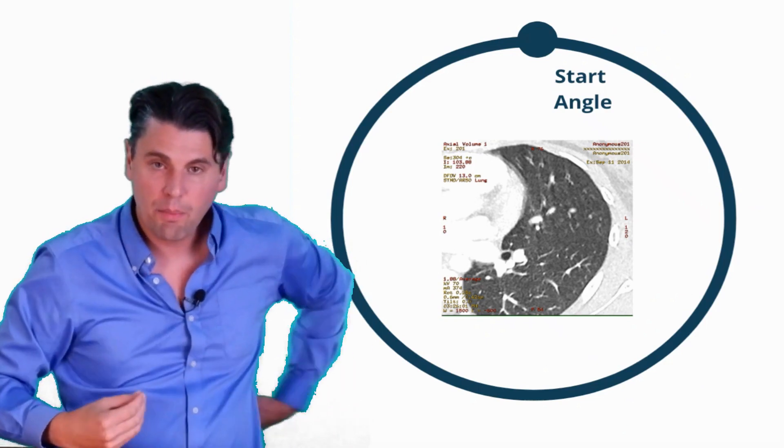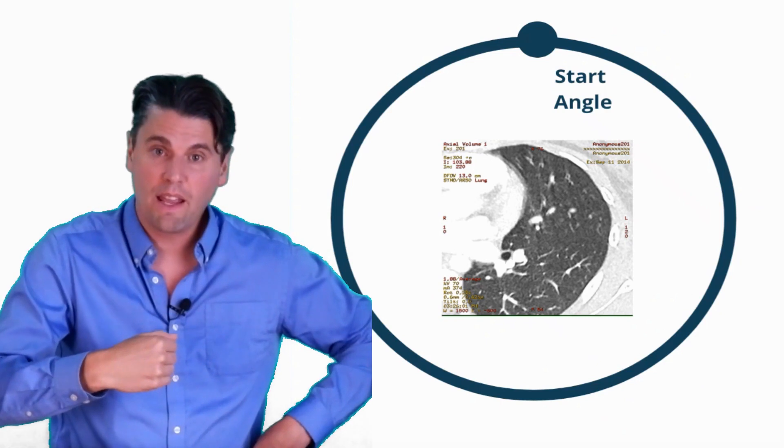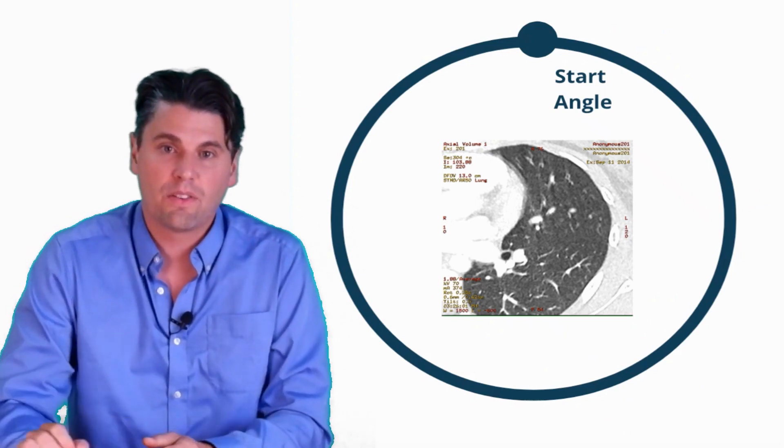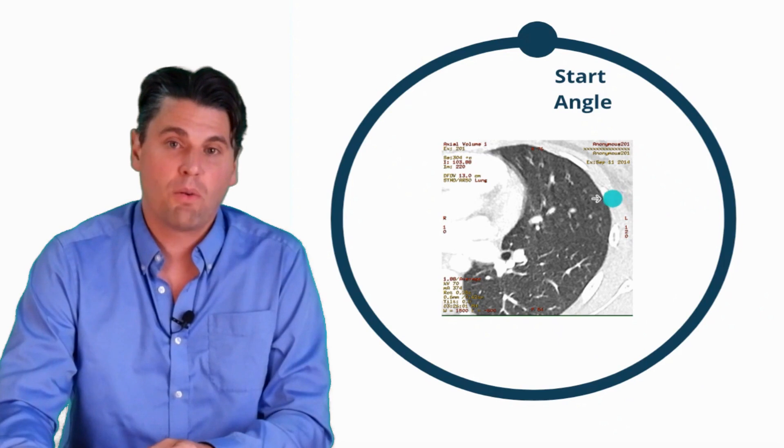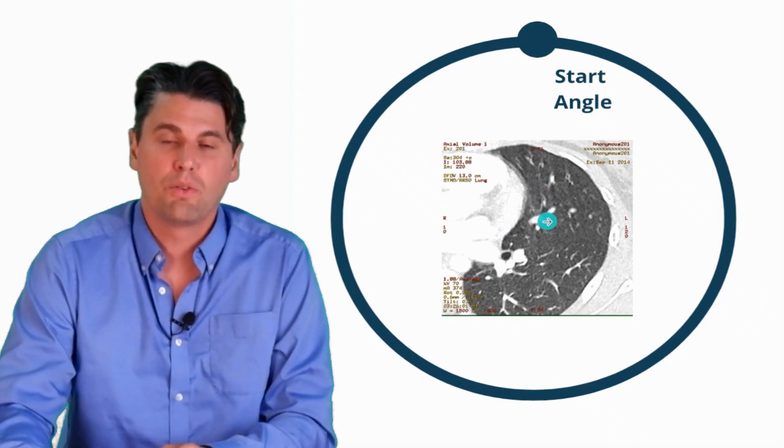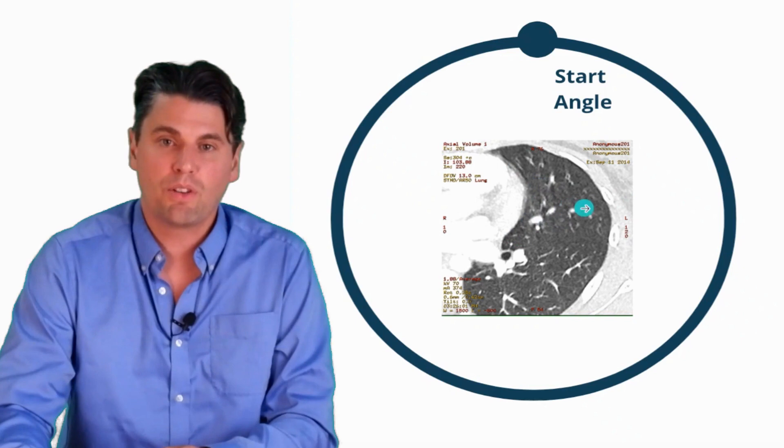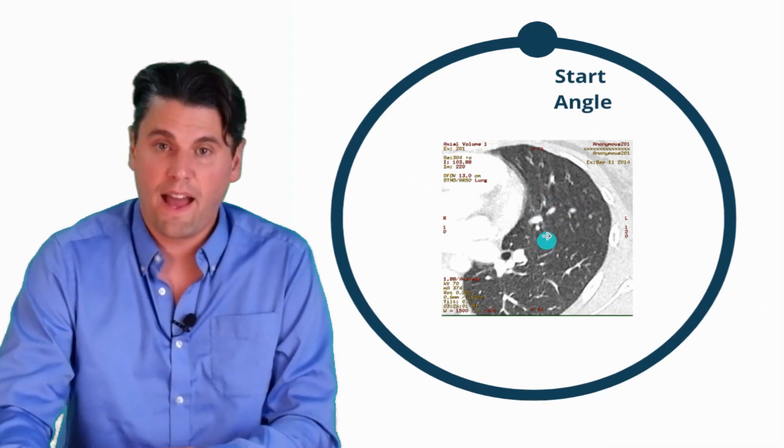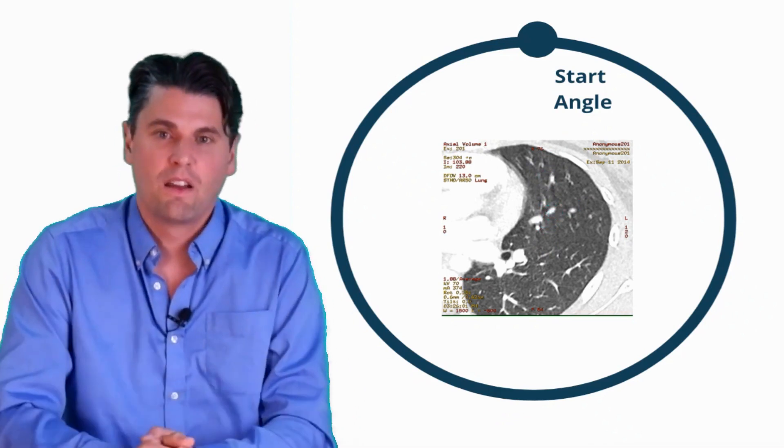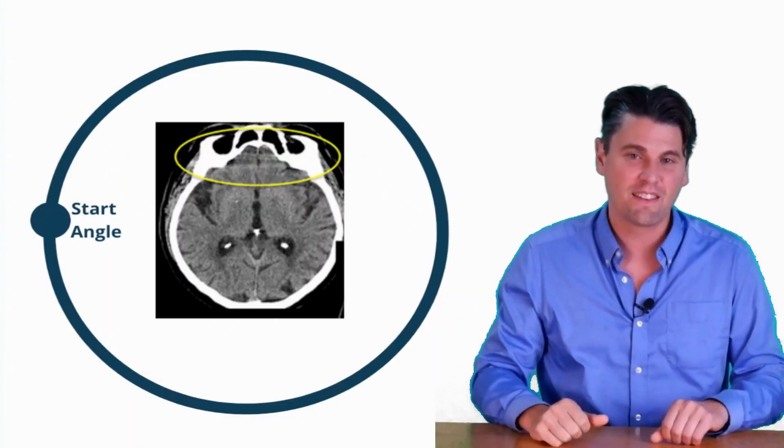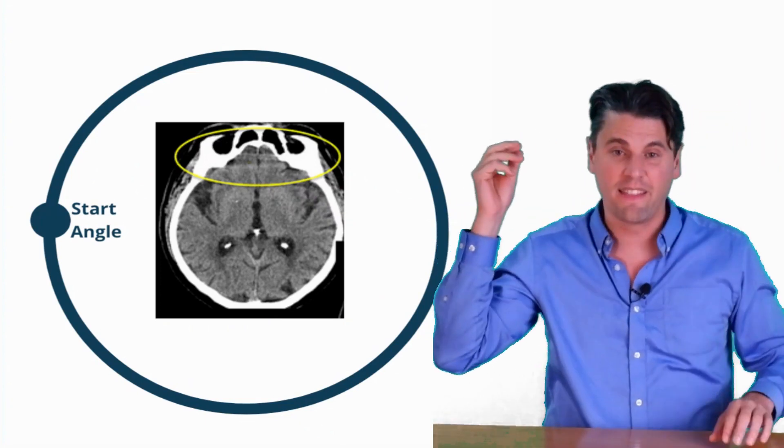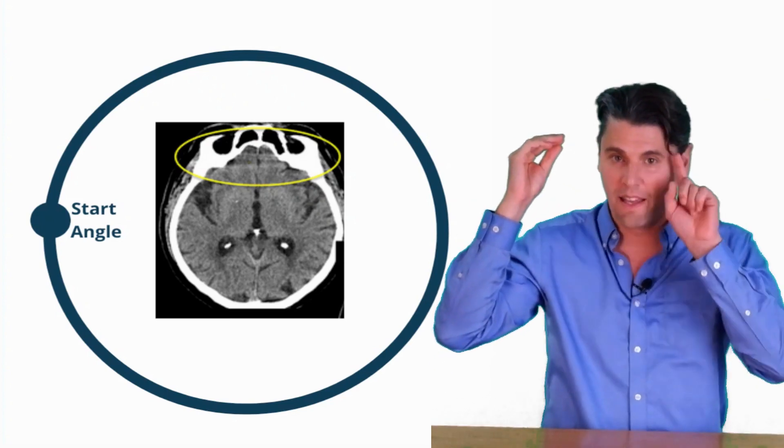So what does that look like in the case of our actual medical images? If we had a starting angle right here, then we went around the patient, and then the ending angle is also right here, and the lungs are right here in the middle. If we did just an axial scan and we used a full axial scan, what actually you would get if there was motion of the cardiac anatomy and then of the lung anatomy directly adjacent to the heart, you can see because that motion was actually in this direction that there's actually going to be artifacts that are coming in this direction.